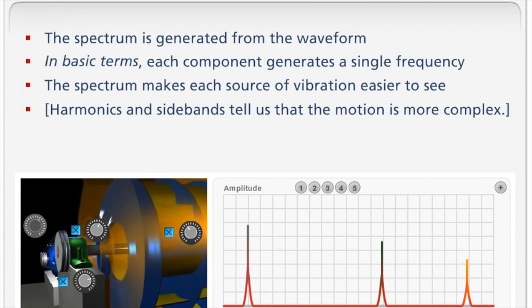is that what we've shown here is this is the frequency. And I'm simulating this as if right now it will vibrate at 30 Hz. Because I've got 10 blades, so therefore the vibration from the fan would be at 300 Hz. And the better way to say it is, well this is 1x, 1 times the running speed. I've got 10 blades, so this peak would be 10x.